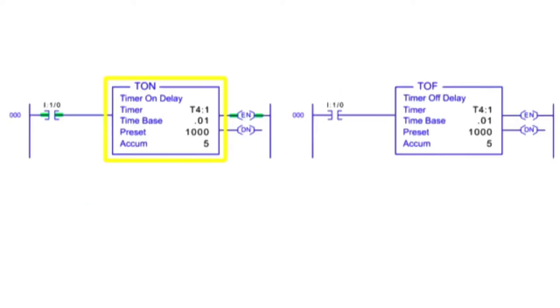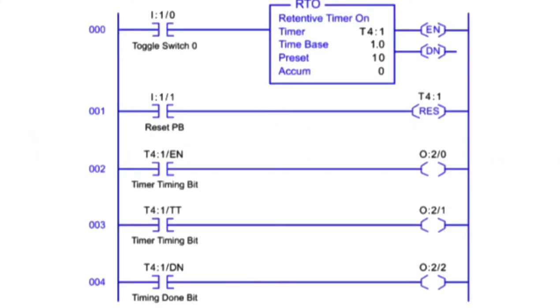Timer On and Off Delays reset when the input conditions change true or false depending on the timer type. For applications requiring the accumulated time to be retained if there were a system fault or the input condition goes false, a Retentive Timer On is used.